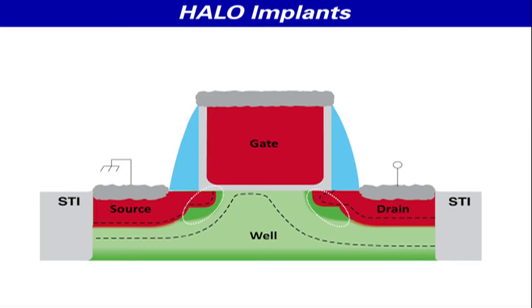So while the requirements for halo implants are such that better than 1 degree control is desirable, we have identified in our testing over an extended period of time, almost 6 months, that we're able to achieve control better than 1/10 of a degree in some cases. So it appears that we're well within the requirements for what is needed for most halo implants.